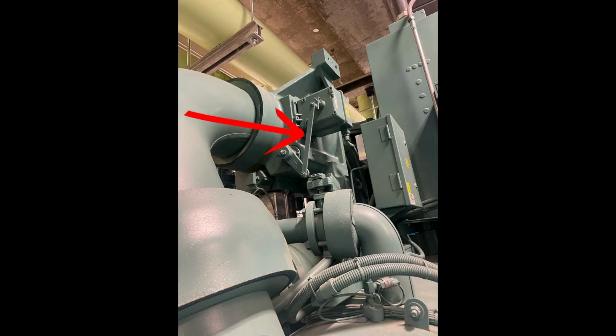Now, in the event that you're coming in behind somebody else who maybe didn't do it correctly, but you're still having issues, in that scenario you come back to this linkage bar may be part of your problem. If they did not verify the actuator was in the correct position, and if they did not verify that the shaft was fully pressed, and like I said, put a little pressure on it to make sure that it is fully closed, not just ever so slightly cracked open, you don't want that. Then you can install the actual arm and set it in place.